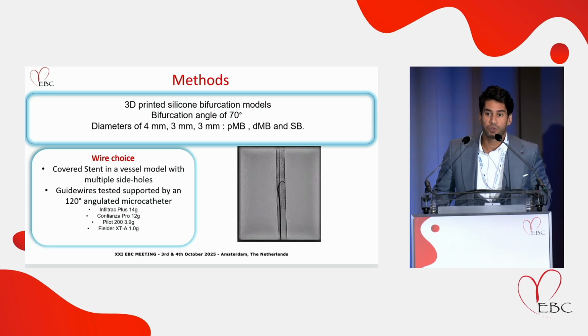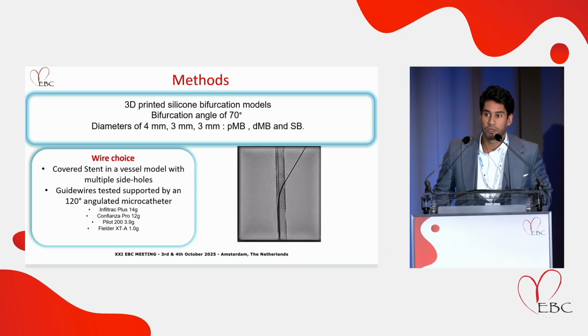The success to cross the covered stents means that we managed to puncture or fenestrate with the microcatheter, but also the tip should not be damaged and the microcatheter should be able to follow up, and all of that should be under 5 minutes, which is an arbitrary cutoff that we decided on. Because anyhow, we are dealing with a perforation and we don't need that to take long.